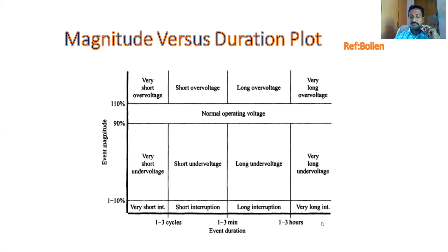Then you come back. Above 110% and the time duration is 1 to 3 hours, long over voltage. If it is below 90%, time duration 1 to 3 hours, it's a long under voltage. If it is below 10%, time duration 1 to 3 hours, it is a long interruption. More than 3 hours, above 110%, very long over voltage. More than 3 hours, below 90%, very long under voltage. More than 3 hours but below 10%, very long interruption. So this is the characterization of power quality problems, identified based on magnitude versus duration.